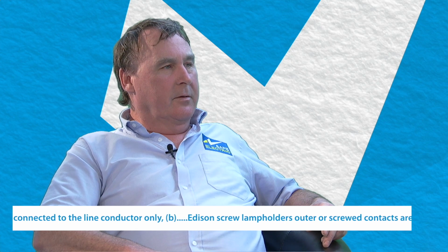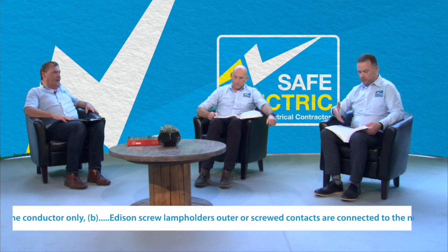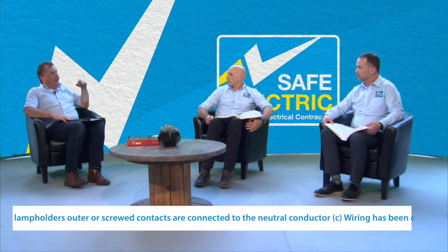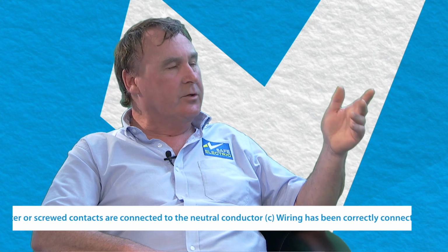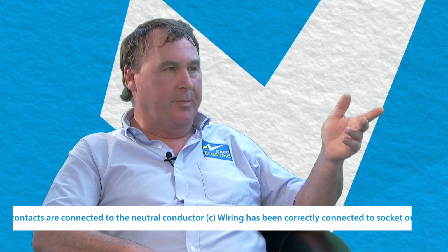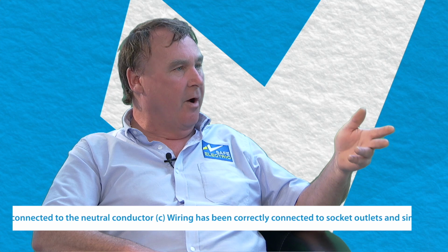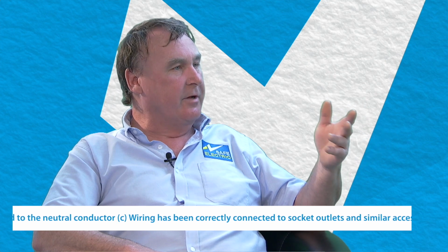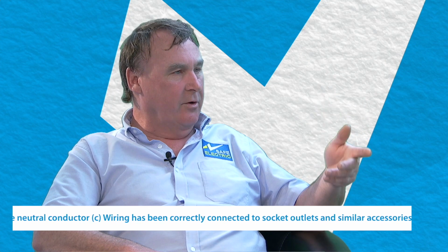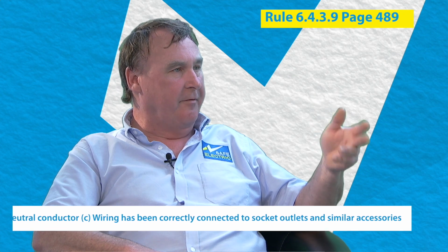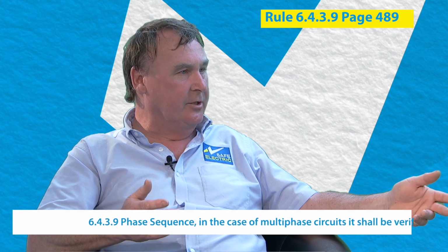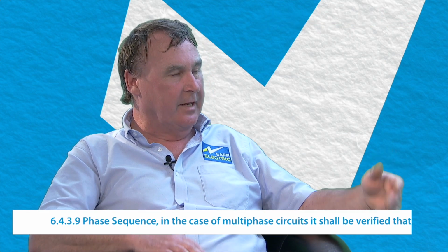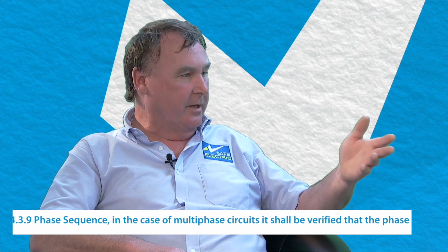Some contractors are using the loop impedance test to verify polarity, but it is important that we know that within these rules, IS 10101, we do require this test to be done pre-connection. I noticed in the new rules that we used to have two post-connection tests, fault loop impedance and RCD tripping or operation times. We now have three post-connection tests: fault loop impedance, RCD tripping times, and phase rotation. Obviously, the phase rotation will only be relevant in a three-phase installation. But if you're signing off on a three-phase installation, it will be important to carry out your phase rotation test.